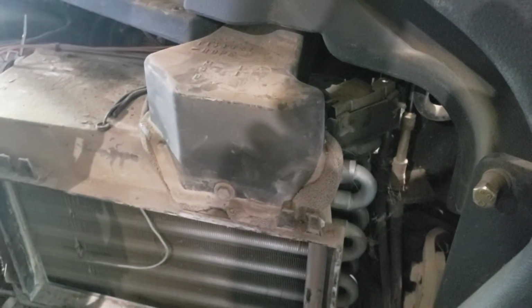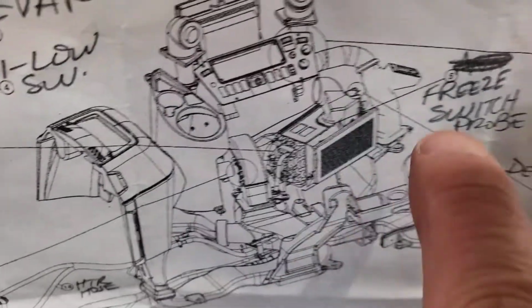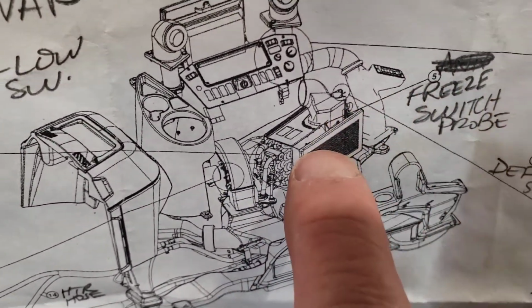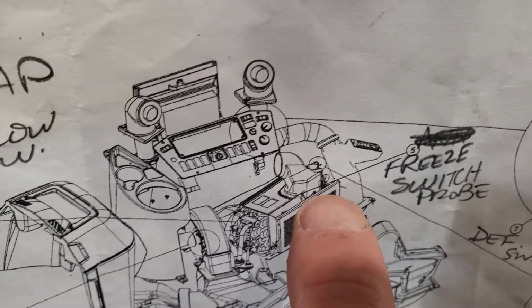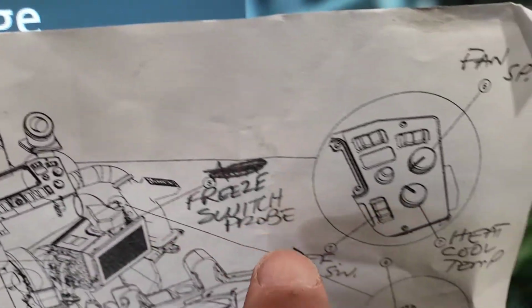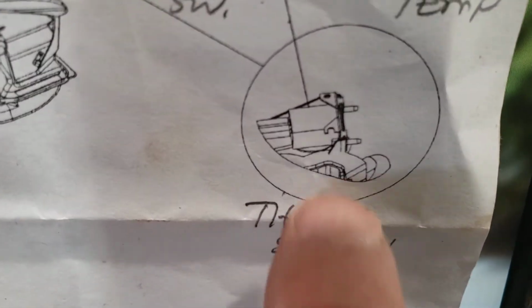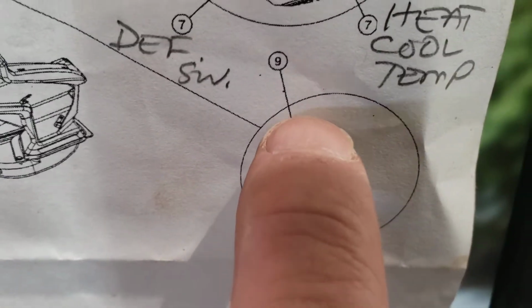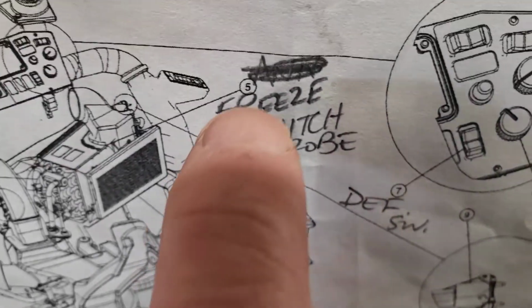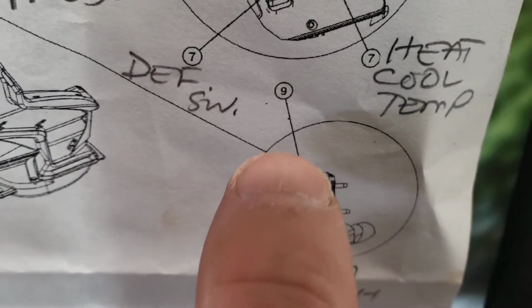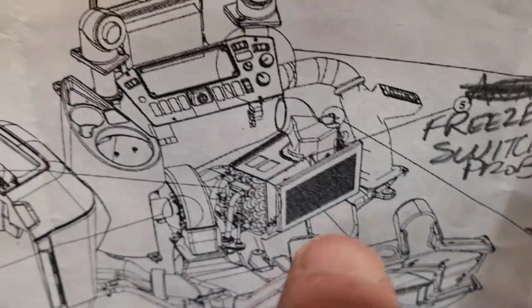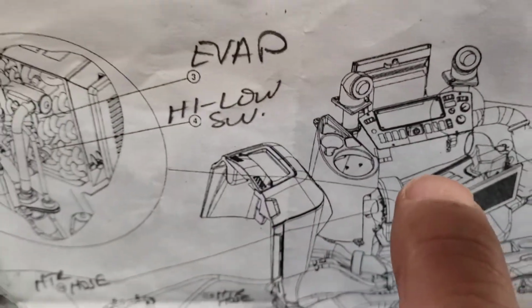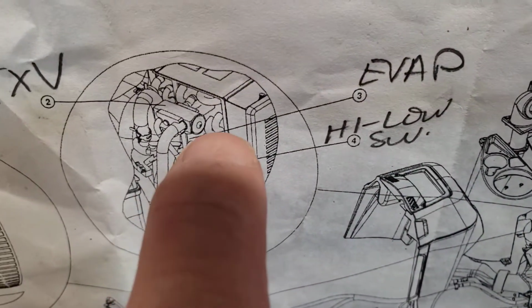So that's where our evaporator is there. They call that a freeze switch probe that's coming in to the evaporator, and then that line comes around and connects to this thermostatic switch, which is number 9. So the probe itself looks like it's number 5, and then the switch, thermostatic switch, is number 9. And there's our evaporator. They've just zoomed in on this area. You can see where the evaporator is.